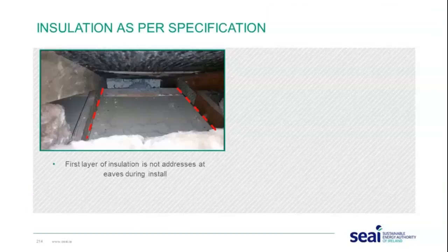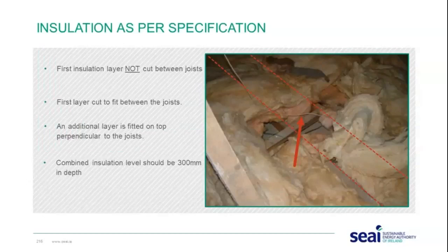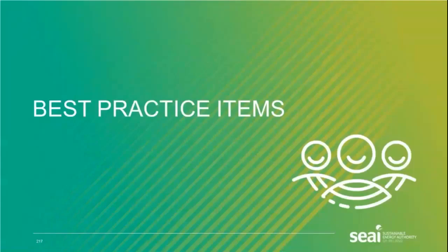Poor workmanship shows heavy duty electrical cables covered by insulation. Good workmanship shows heavy duty electrical cables all lifted on top of the insulation. Another installation issue: at the edge of the eaves, the first layer of insulation is not addressed during install — mould will form on the ceiling beneath. Ensure insulation is pushed all the way to the wall plate while maintaining adequate soffit ventilation. The first insulation layer should be cut between the joists, not raised across them; the additional layer should then be fitted on top and perpendicular to the joists.